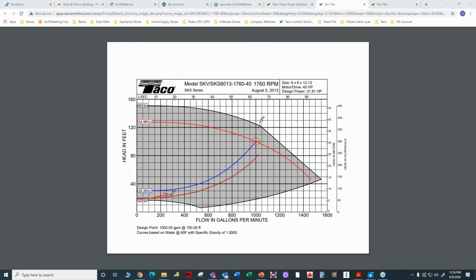And then this area inside here between these curves is the energy savings that takes place when you get more accurate data based on actual field conditions. So this was the curve from the factory, and then this is the actual curve that you want to operate the pump at. And the area between those two curves is the energy savings. So hopefully that answers some questions about control head, minimum pressure drop at minimum flow, and how you can use ProBalance to find the actual pressure drop at the design flow and the actual pressure drop at minimum flow.